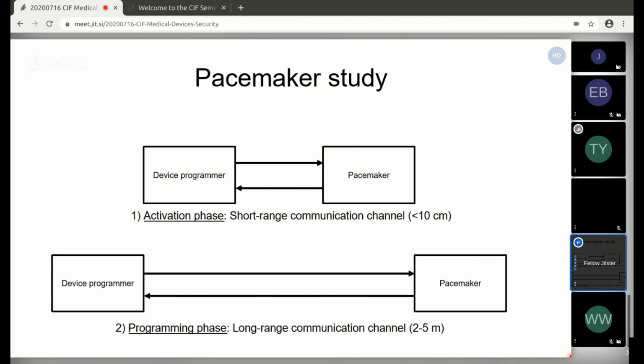using the device programmer. Typically this is done in two phases. First, there is an activation phase where the device programmer activates the wireless interface of the pacemaker. Typically this is done by placing the device programming head on top of the patient's chest where the pacemaker is implanted. By placing the programming head there, some messages are exchanged between the device programmer and the pacemaker, and at the end of this phase, the wireless interface of the pacemaker is active. It's important to know that this happens over a short-range communication channel. The programming head needs to be really, really close to the pacemaker for this to happen. Then once the device has been activated, the device programmer and the pacemaker typically communicate over a longer communication range, which is typically 2 to 5 meters.